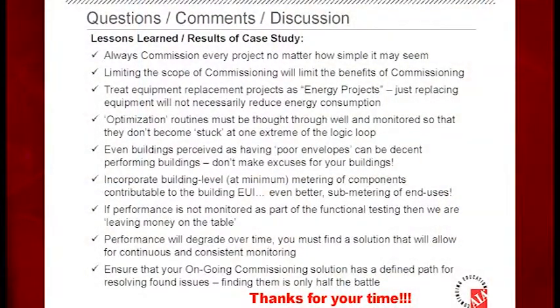Here's Bailey Middle School. Here's our case study project. So you see our 51 there, a 68% EUI reduction overall in the 2 year period. And then GLA, which is our Global Learning Academy, that's that newer school that was good, and it kind of went up, and then we said, man, what happened? Well, let's put it on our program, and we push it back down. So in the 2 years since we've been monitoring that one, we've reduced the EUI 19% on that one.